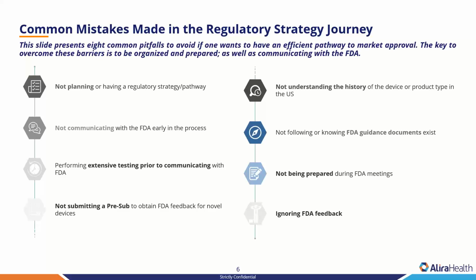So some common mistakes are, again, not planning or having a regulatory strategy or pathway, not doing your due diligence in terms of researching what is the classification of this product and what is the pathway forward. Is it a 510K? Is it a novel product that just falls into de novo? And again, not communicating with FDA early on in the process. Again, that pre-submission process is very valuable, and it's a tool that I highly recommend utilizing if there are any questions in the classification of your system. Another mistake can be performing extensive testing prior to communicating with FDA. You don't want to complete animal studies that FDA are going to object to what was done in that animal study and require you to repeat it. So again, that early pre-submission process is valuable in communicating that information.